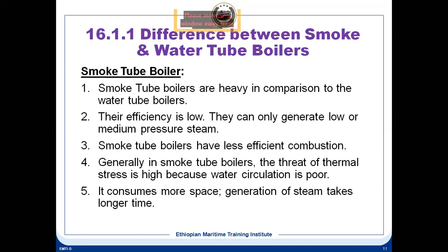It's not the combustion. Combustion will be same, but the heat transfer is different. The heat transfer is poorer. The heat transfer in a smoke tube boiler is poorer as compared to a water tube boiler. So basically, the thermal efficiency of a smoke tube boiler is lower.